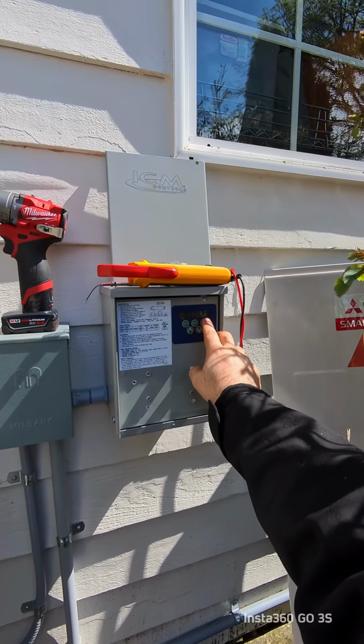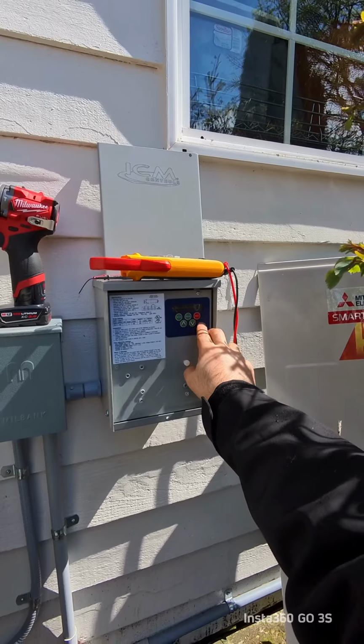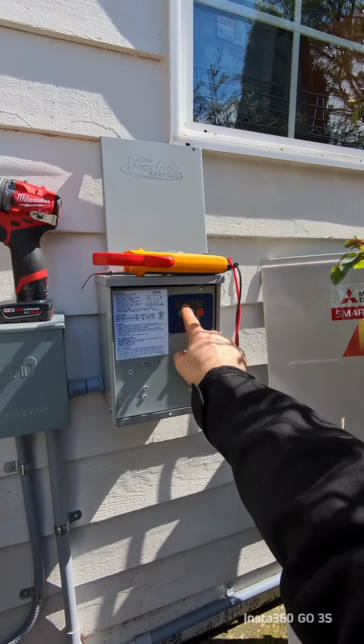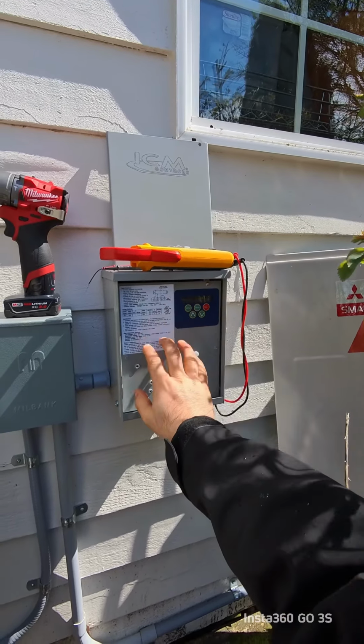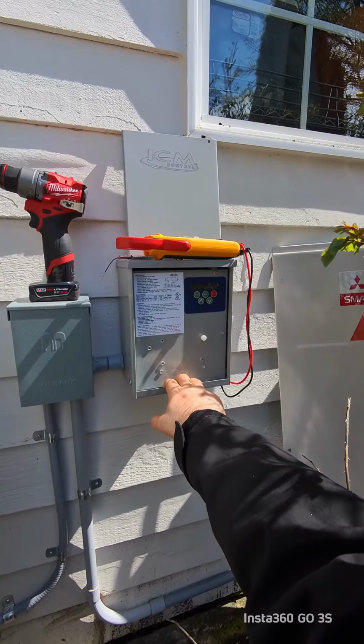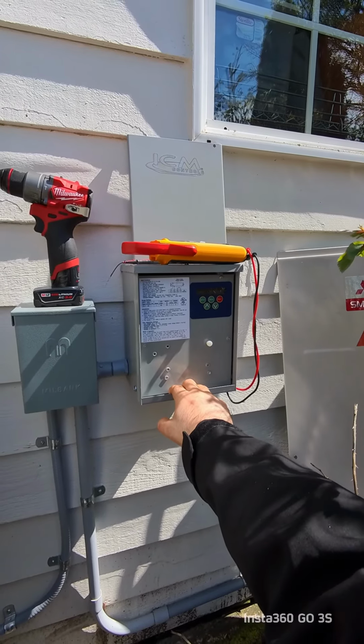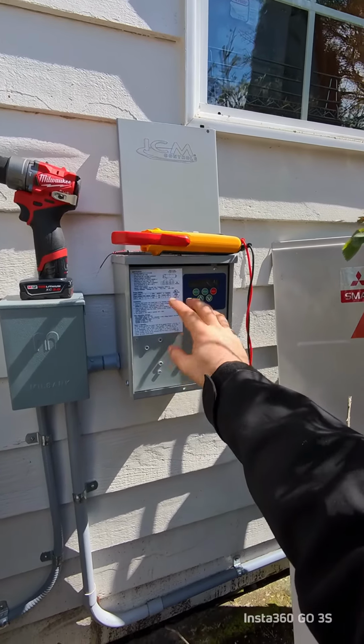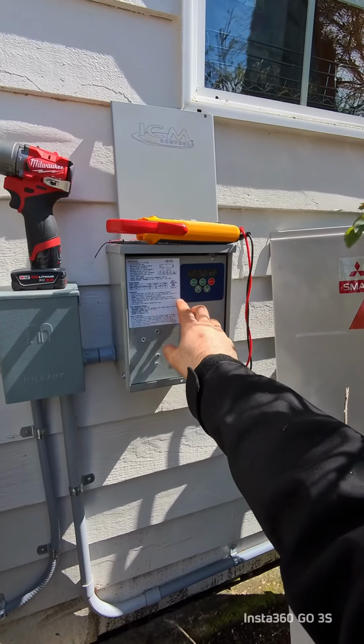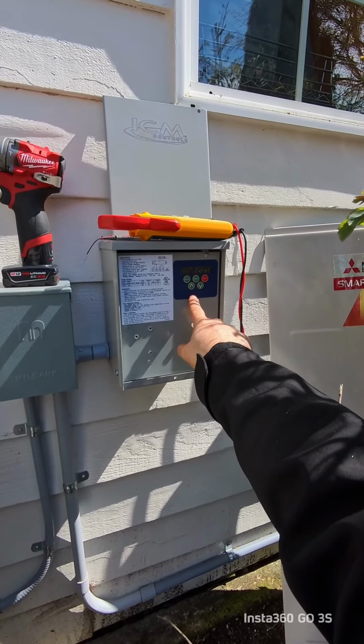So right now, when I had clicked the fault button earlier, it had faulted at 253. So this ICM unit did its job sometime in the past and cleared. So we had a voltage spike, it turned off, but it turned off for about 4 or 5 minutes.